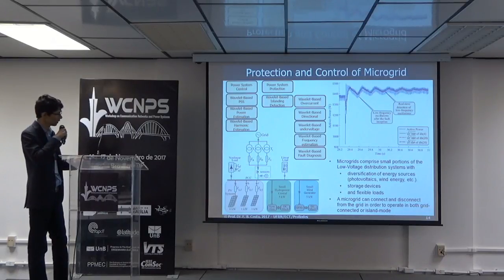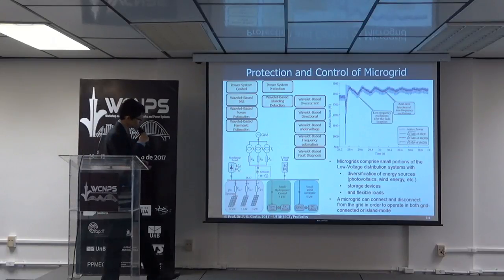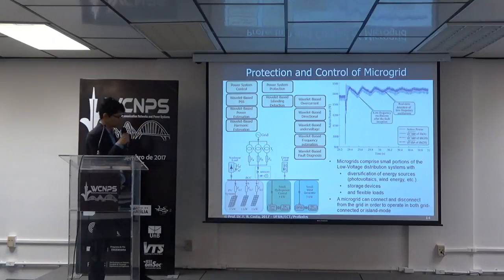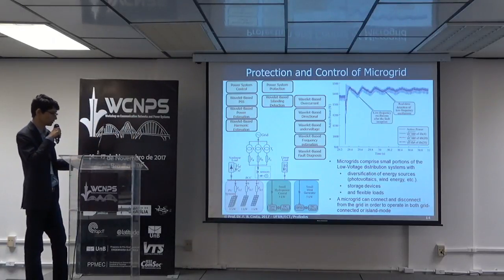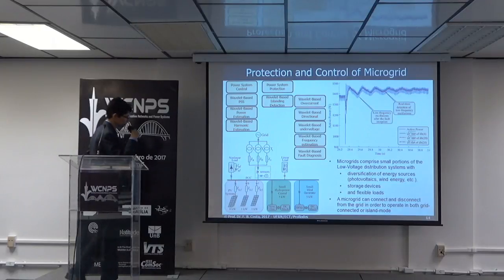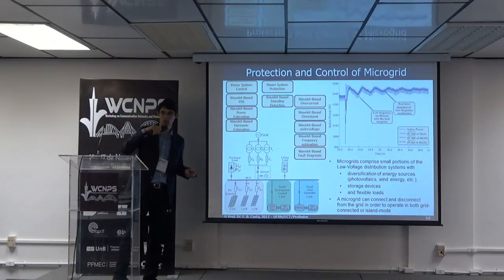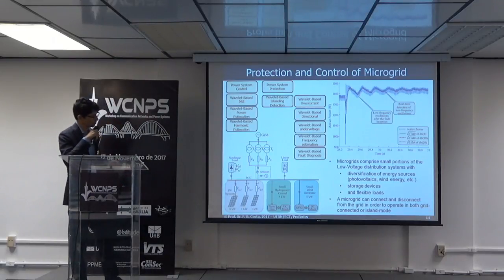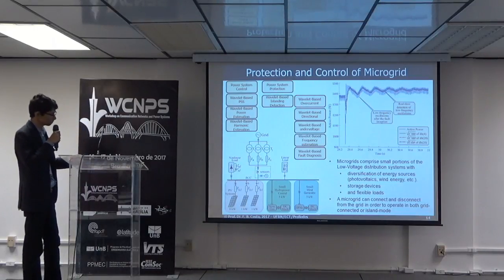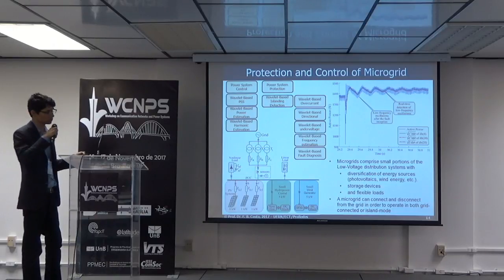For instance, if you have a fault in the main grid, the protection system must detect this fault and disconnect the microgrid as soon as possible. So the microgrid should work normally during a specific time according to its capacity. And if the generation is not able to feed all the loads, specific loads could be disconnected. There is no problem in this case. But important loads, such as, for instance, a hospital, traffic lights, should be fed, okay? And so the control and the protection must work together.